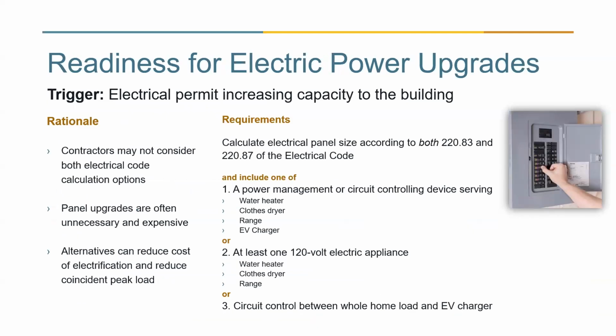And this is a slightly less common situation, but if through an electrical permit the panel capacity is actually being upgraded, we want to make sure that it's well thought out. So in addition to the electrical panel size upgrade, we want to make sure that it would include some sort of load management system, whether it's an appliance by appliance load management system, or a whole home load versus EV charger load, or optionally at least provide one electric appliance that is just a 120 volt electric appliance.